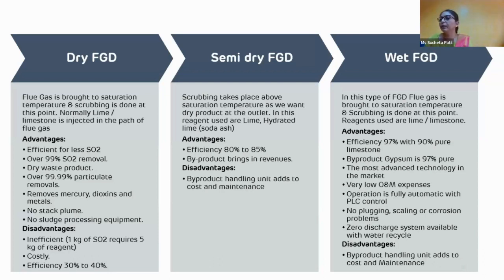Then another type of FGD with lime, it is wet FGD. In this type of FGD, gas is brought to saturation temperature and scrubbing is done at this point. Reagent used is limestone. Advantages of this FGD are efficiency is around 97%, with 90% pure limestone we have to use. Byproduct gypsum is 90% pure, and most advanced technology. This is the most advanced technology in the market, and very low operation and maintenance expenses. Operation is fully automatic with PLC control. No plugging, scaling or corrosion problem. Zero discharge system available with water recycle. But this system also has one disadvantage. Byproduct handling unit adds to cost and maintenance to the system.